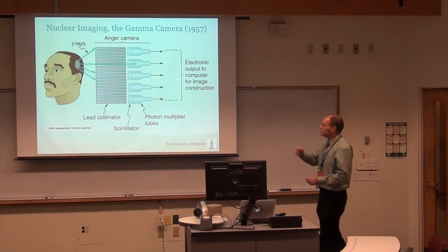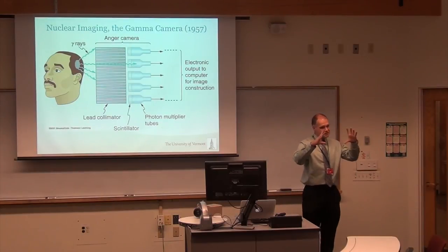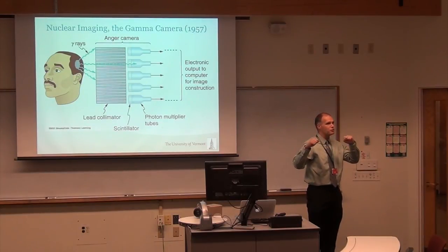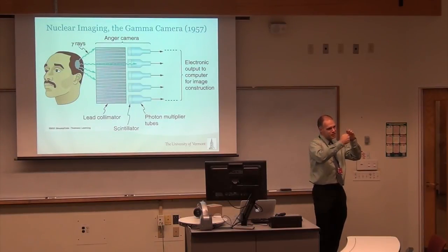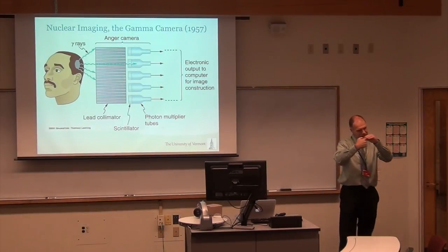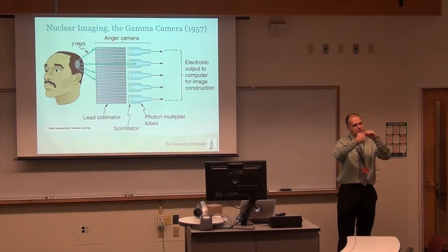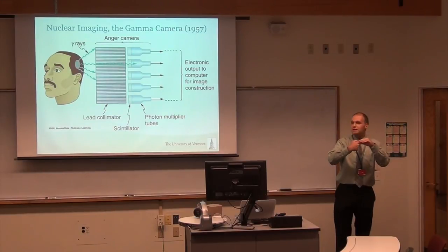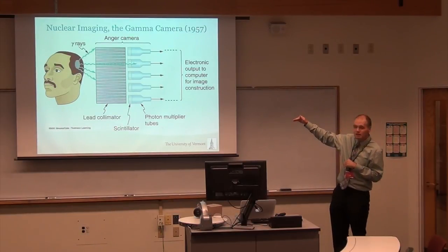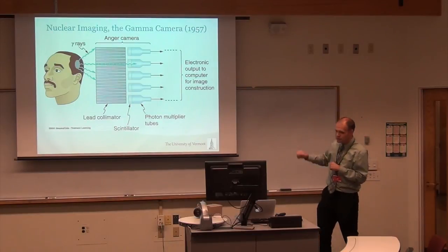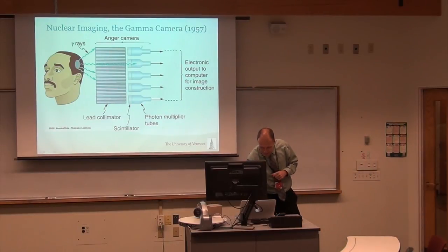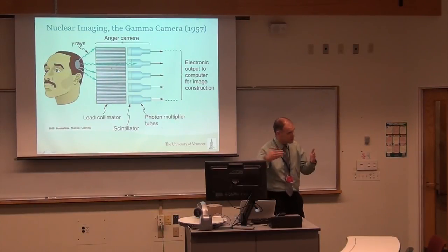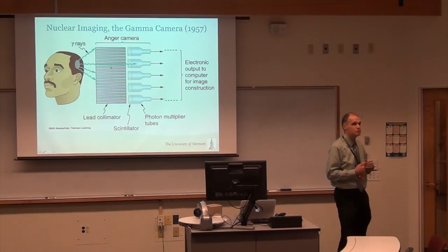So the Anger camera is just based on a lead collimator — a sheet of lead with lots and lots of little holes in it. Because the holes have a certain depth, only gamma rays going in a particular direction will go through the holes in the detector, giving you a parallel beam collimator. So essentially, if you detect a gamma ray in your detector, it must have come straight along that line, straight through the collimator, otherwise it would be blocked.